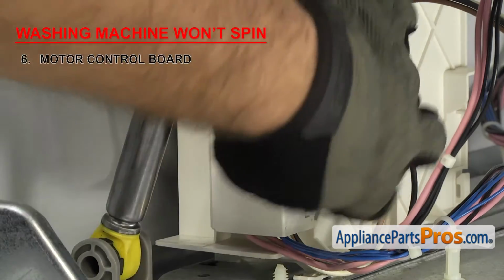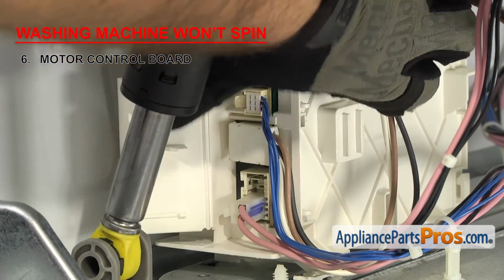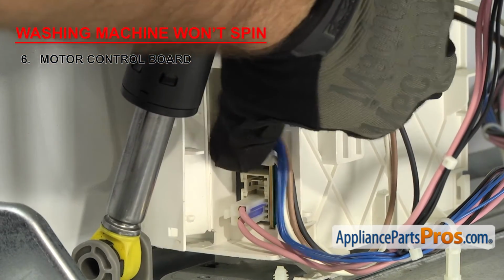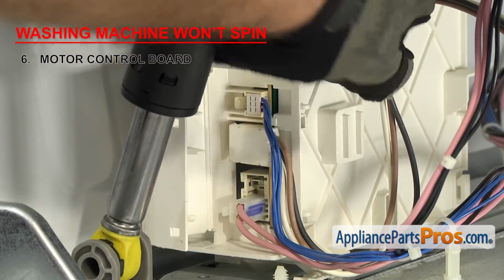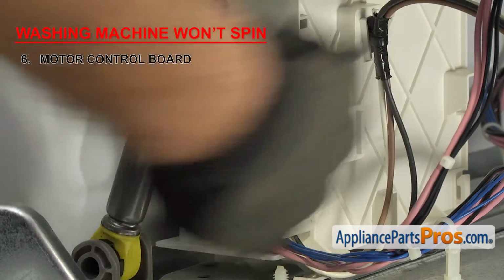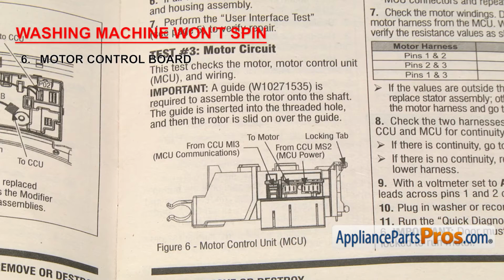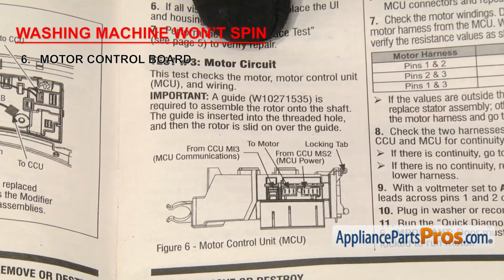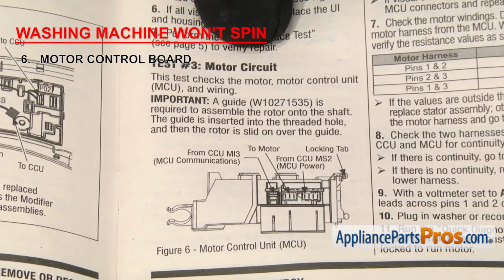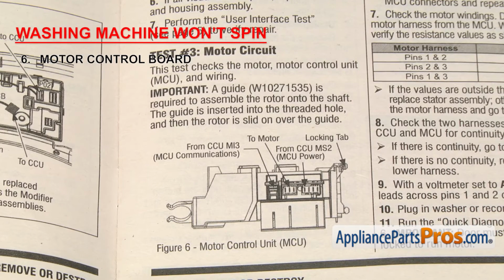First thing you want to do is check that the wiring connections to the board and between the board and the motor are plugged in securely. Also make sure there's no corrosion or noticeable damage to any of the connections. If that doesn't solve the problem, you'll have to get the tech sheet and follow the troubleshooting steps to test the board on your specific model. If it fails, you'll need to replace it.